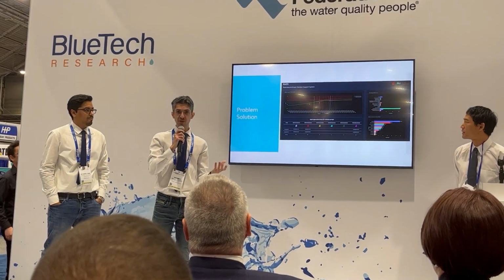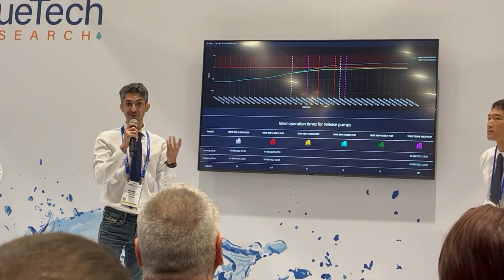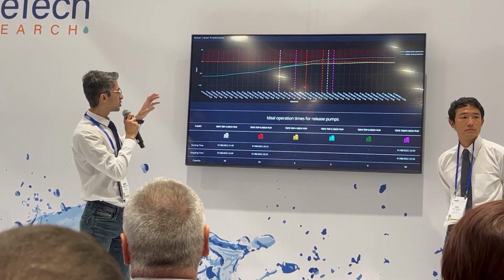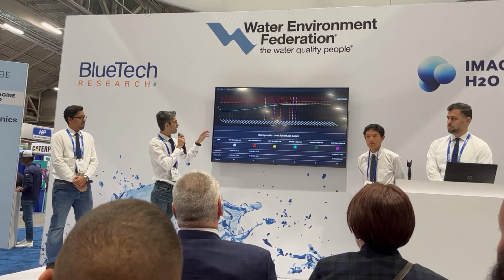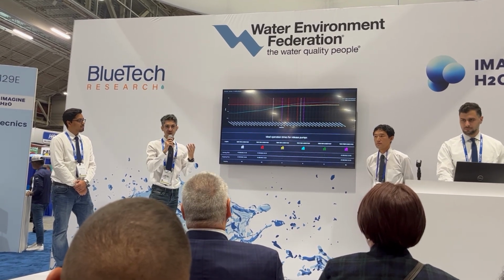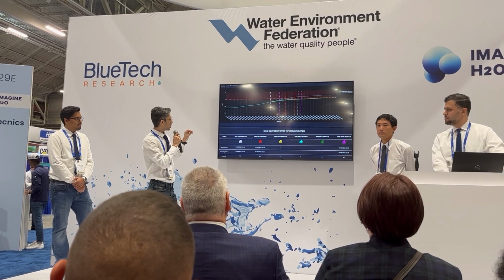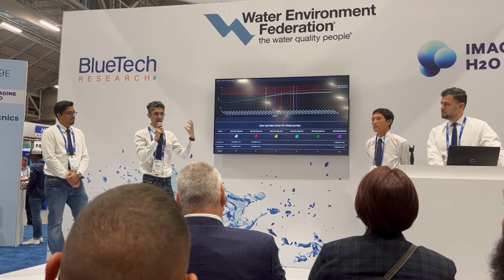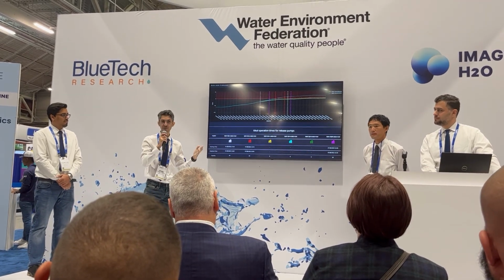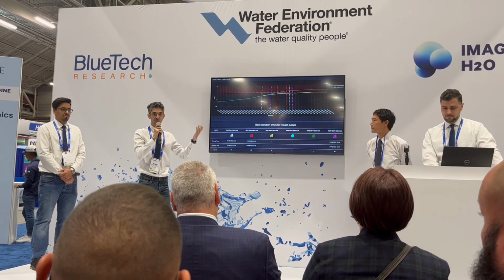We developed graphs to support operators on making optimal and feasible decisions. The operator can use this dashboard to understand what is going on in the facility, and shown in the dark green line, we see what will be the water level in the tunnel for the next 4 hours with a 5-minute frequency. Using this information, our optimization model calculates the best times and capacities for industrial pumps to pump the effluent from tunnel to the wet weather treatment process.